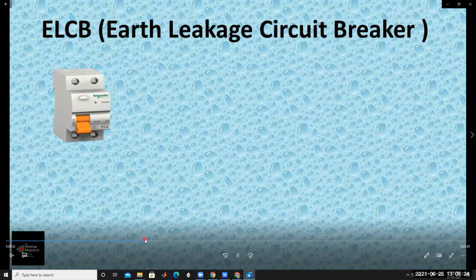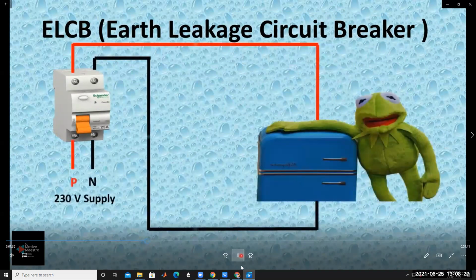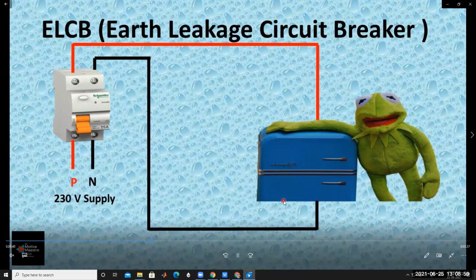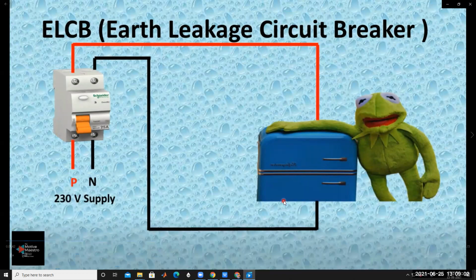So consider this. Generally, the phase wire and neutral wire operate on a 230 volts supply. It is connected in this manner. If you are operating this device, for example opening or closing the door of a fridge, or turning on the switches, while doing these operations, if there is any leakage current, any earth leakage, that fault current passes through the human body. Right or not? The fault current passing through the human body is very dangerous to human beings. That's why the earth leakage circuit breaker is used.